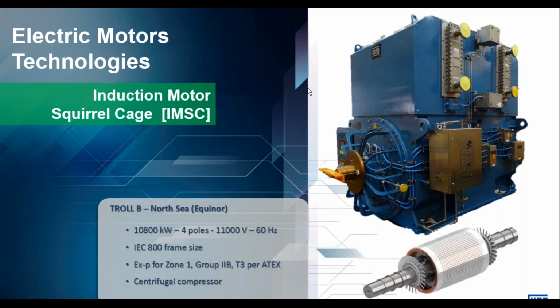Some disadvantages: in the standard design squirrel cage machine, high starting current is unavoidable in direct online condition, and it gives reasonable starting performance, but for very high inertia loads that need a high overload, generally the squirrel cage machine on its own is insufficient.